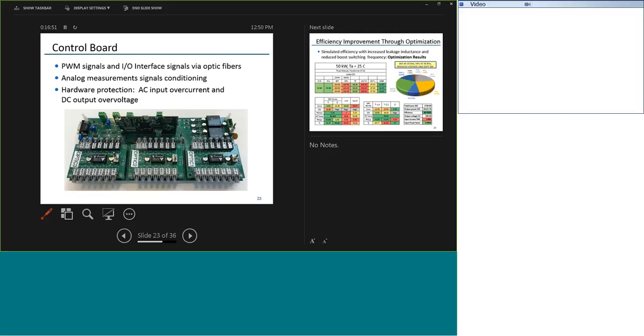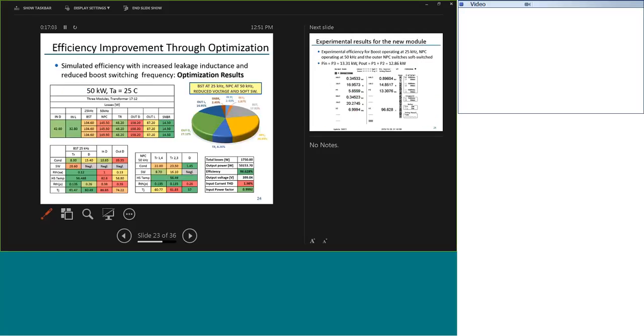Looking at the control board, this is the actual design. We have 3 modules here, one for each of the physical modules of the system, and we're using a TI DSP as shown here. Looking at the system efficiency, we projected a 96.6% efficiency using 25 kilohertz switching at the boost stage and 50 kilohertz for the NPC stage.